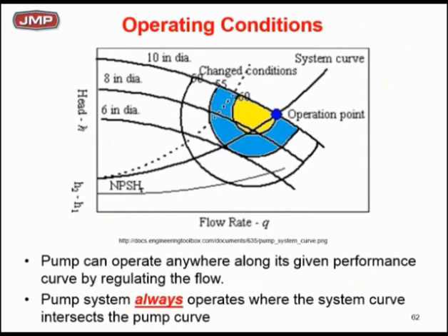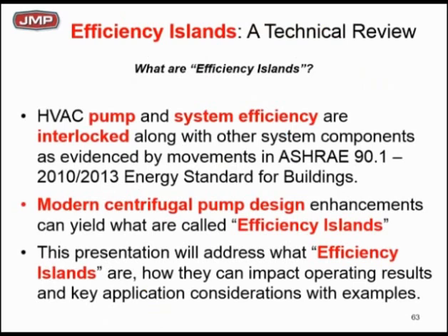And that's where we got to look at the efficiency of the pump and see what's happening. So efficiency islands, we start looking at a little bit. What we're seeing is there's a lot of modern pumps out there, a lot of pump efficiencies out there, a lot of people trying, which is the right thing to be doing, to improve the pump efficiency. Well, it's not all about just looking at that BEP anymore.